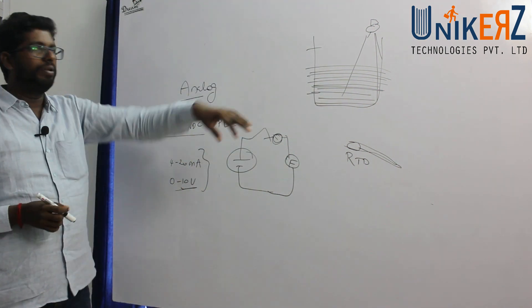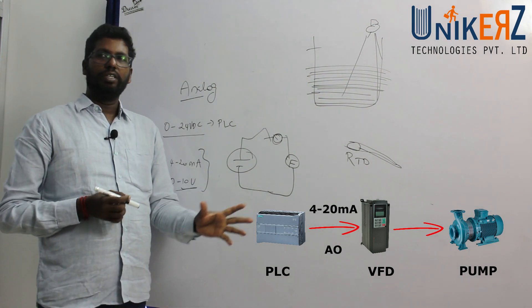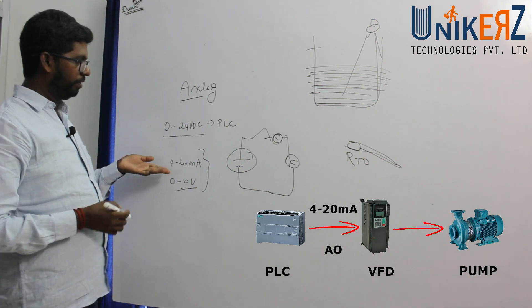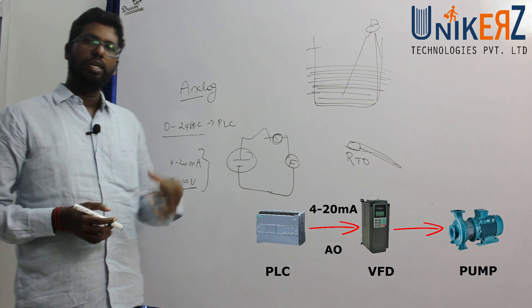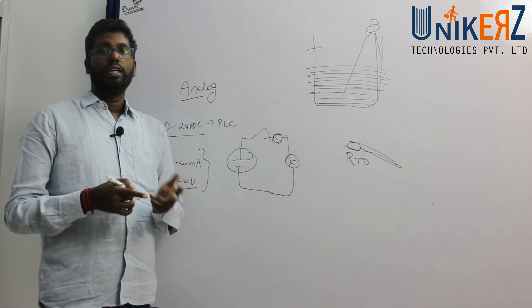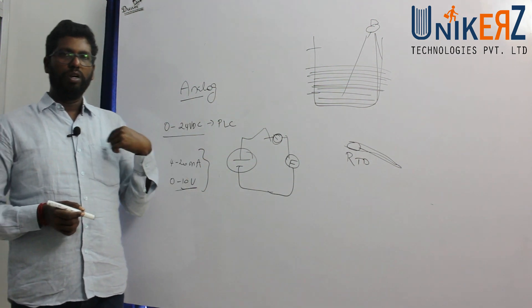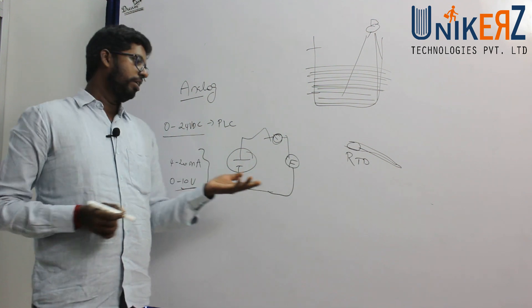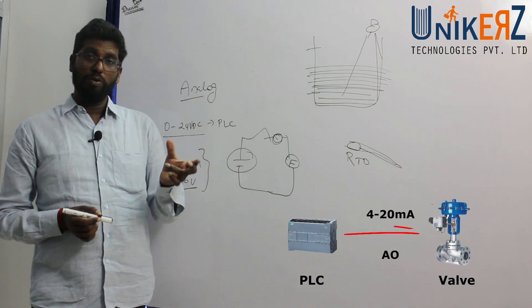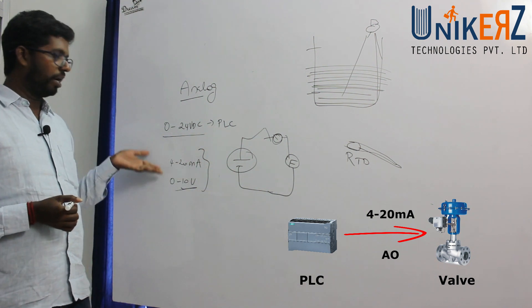For analog output, it is used to control a motor, a valve, or a pump — using 4 to 20 milliamps or 0 to 10 volts. For example, by changing the 4 to 20mA signal, we can control the speed of a lift or control the position of a valve from 0 to 100 percent open or closed. These are analog inputs and outputs.